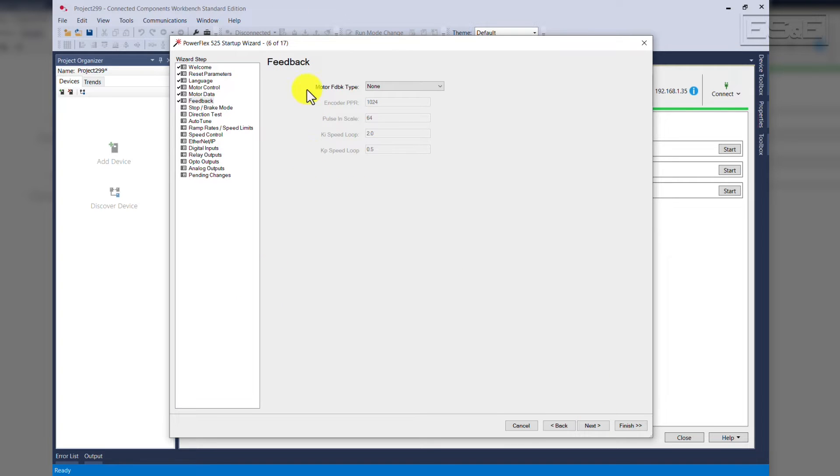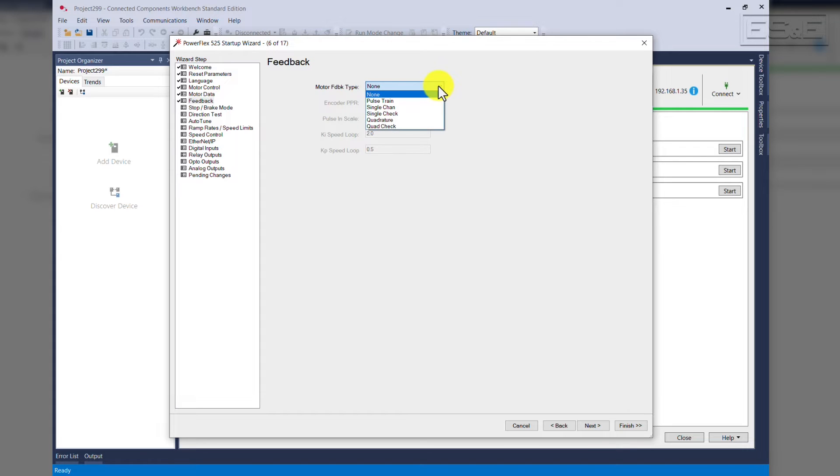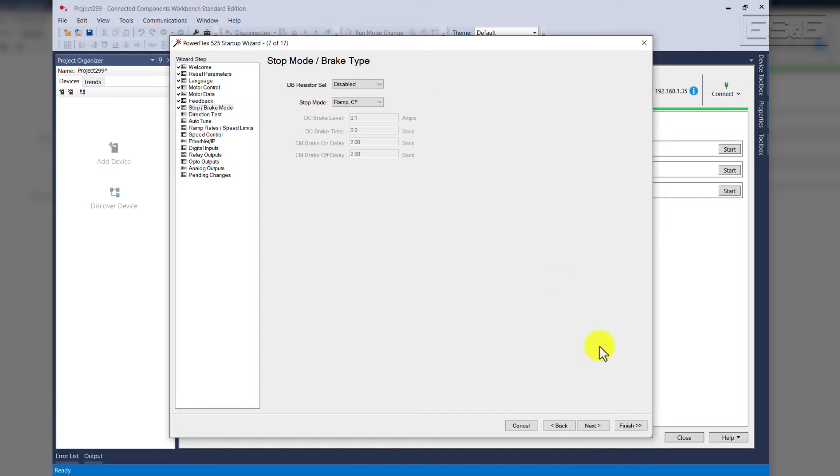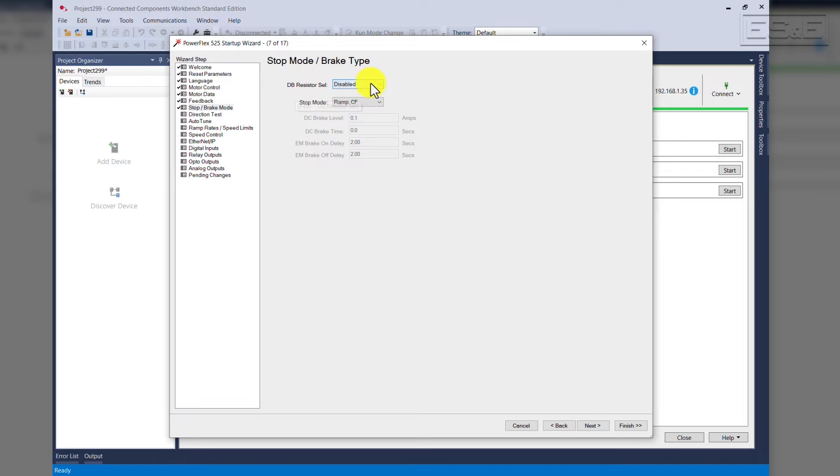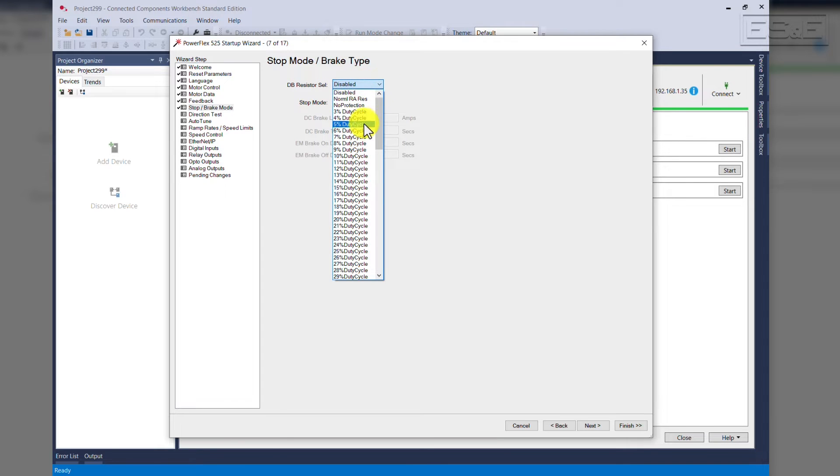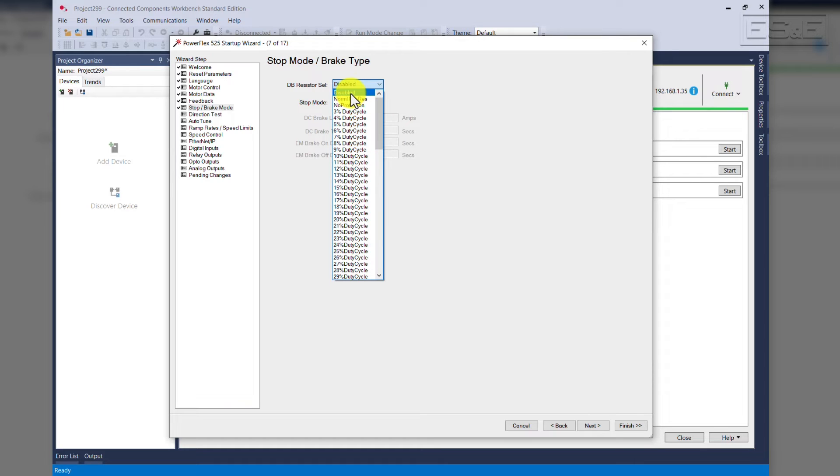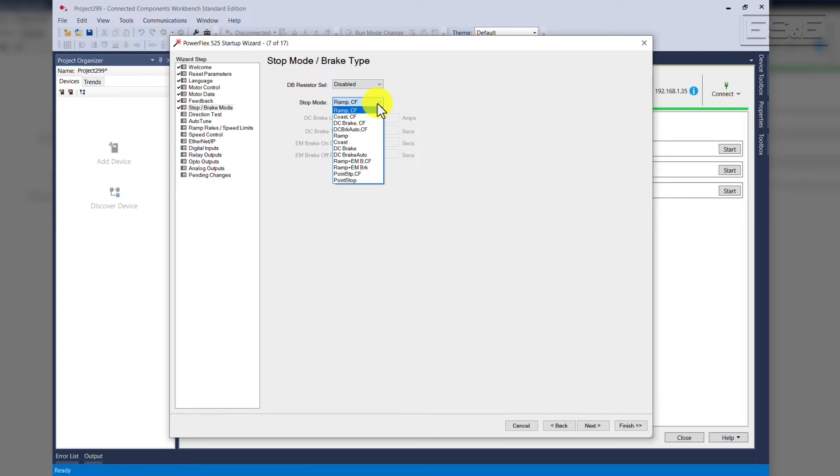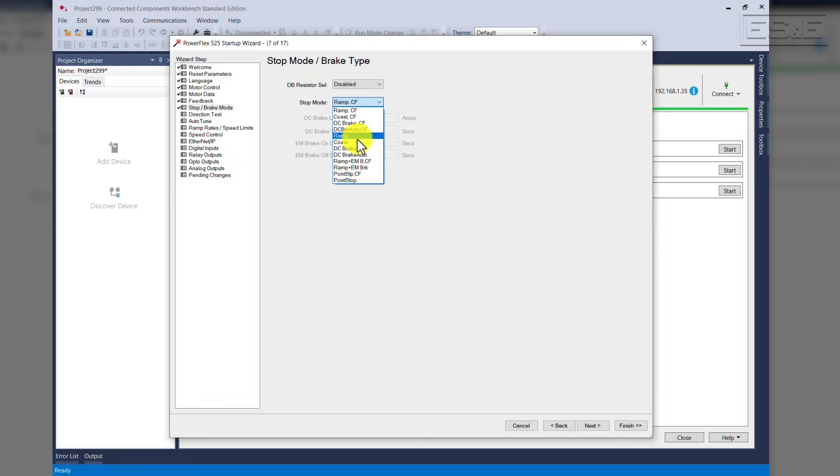This takes us to the feedback screen. If you do have an encoder installed on your application, this is where you will set it. But for our application, we'll select None. Stop mode and brake type, if we're using a dynamic brake resistor, it can be selected here, depending on the duty cycle of the brake. For our application, we will select Disabled. The stop mode, we will set for Ramp, Clear Faults, but other ones can be used, such as Brake, Ramp, Coast, etc.